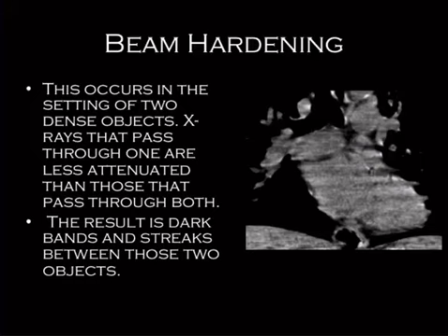And you can fix this a bunch of different ways. You can pre-harden the beam to try to remove lower energy components, like adding a bow tie filter. There's certain software that can be used, but probably the easiest way to fix things is to just position the patient correctly with their arms up, or tilt the gantry to avoid going through too dense things like that.